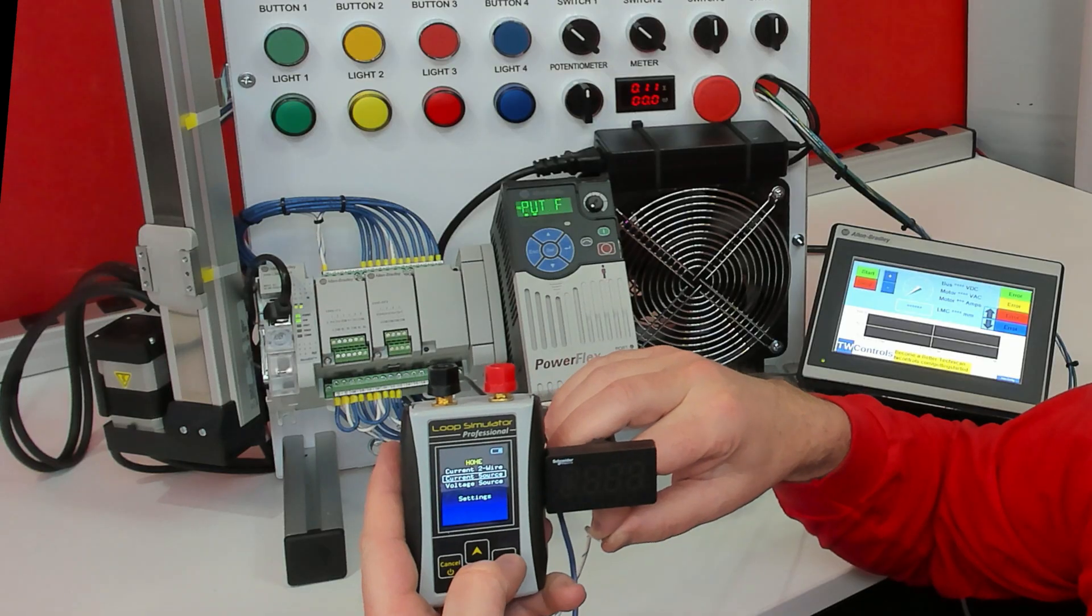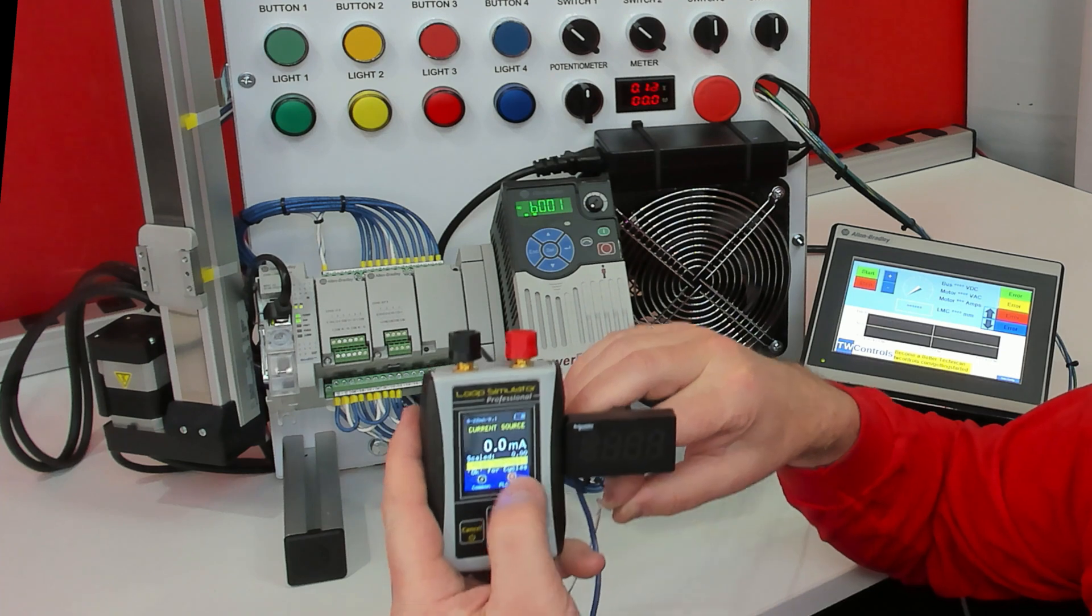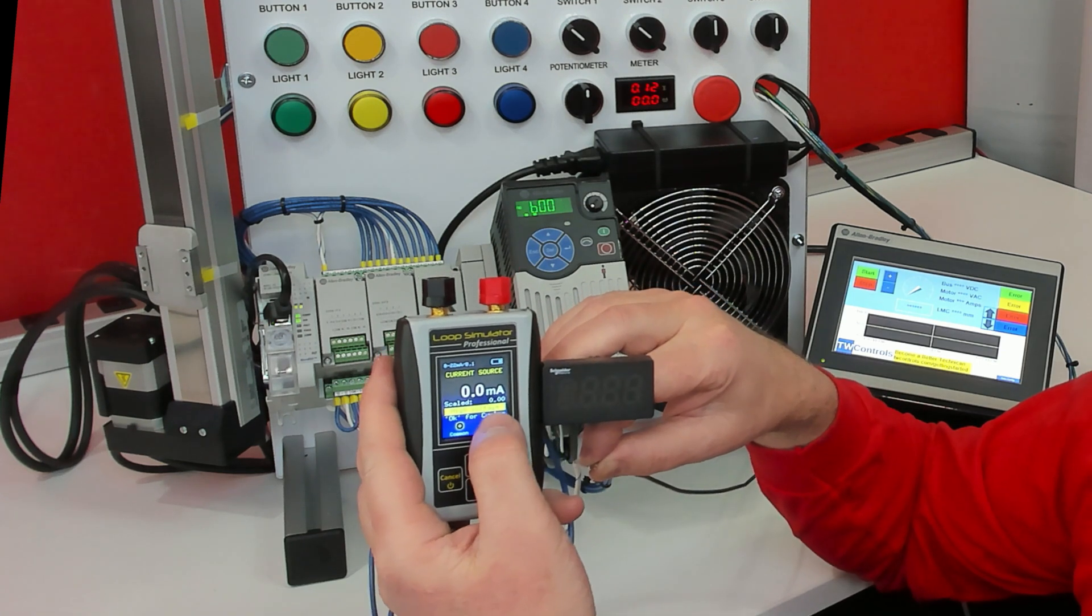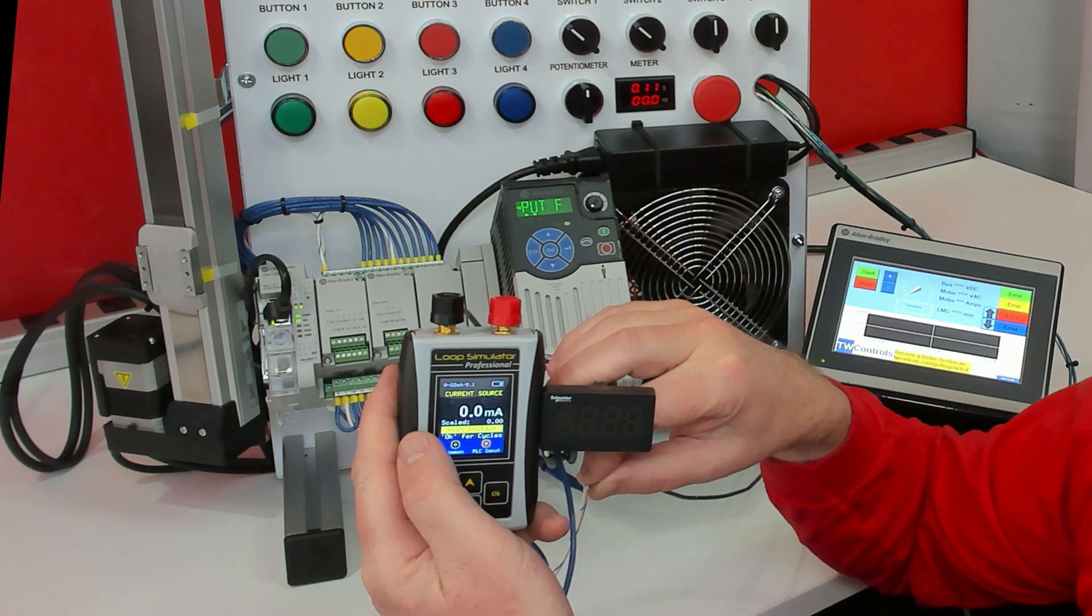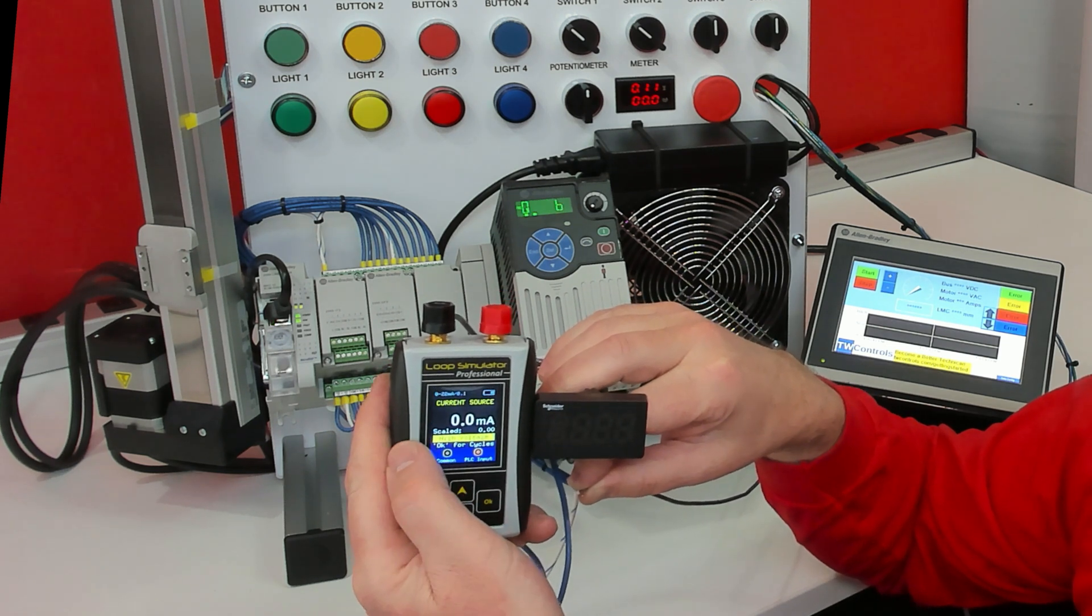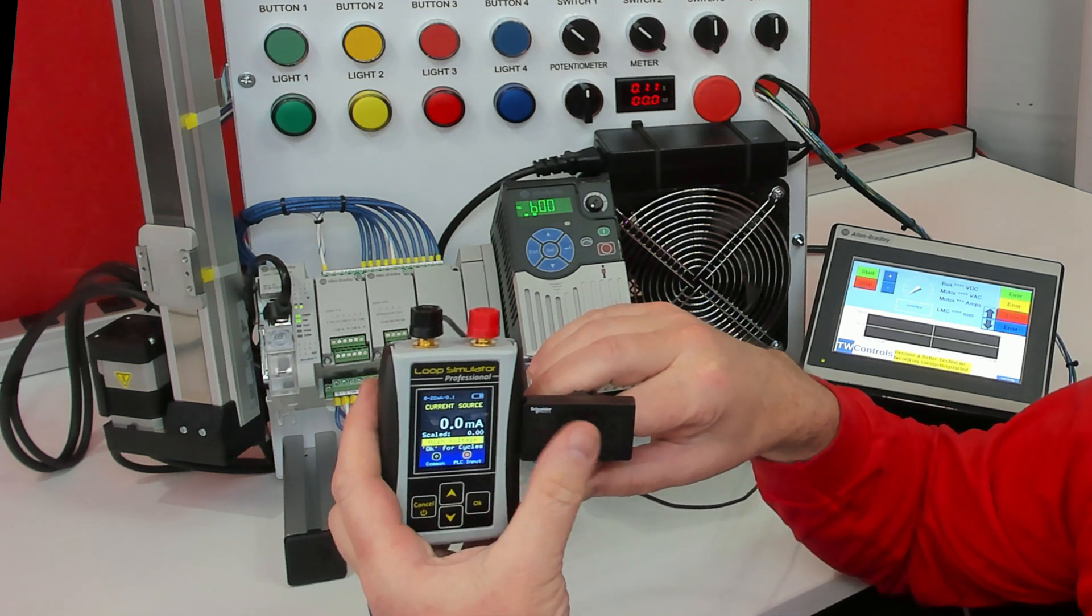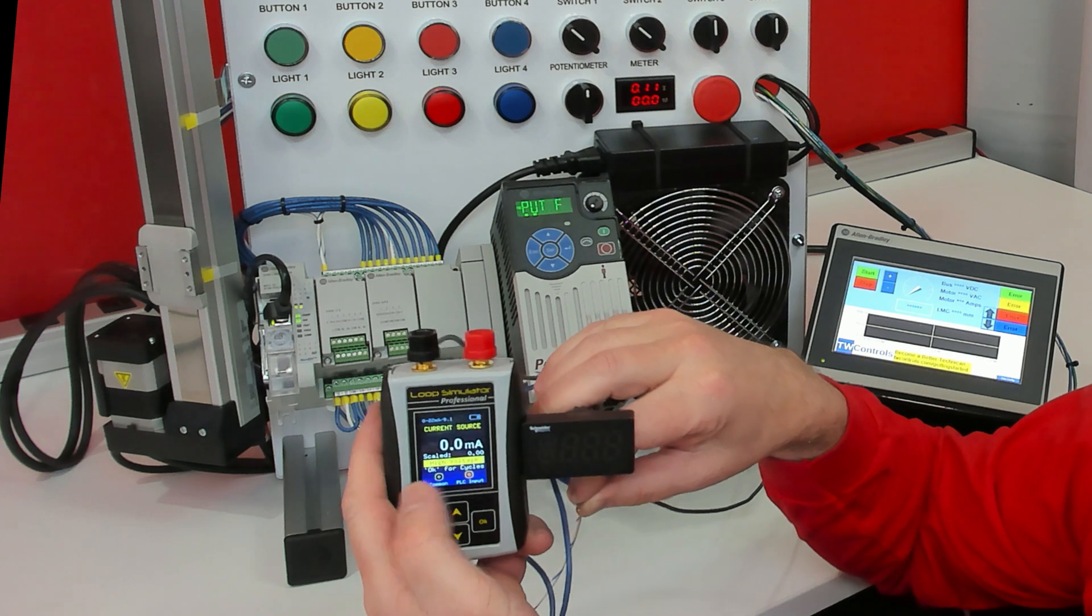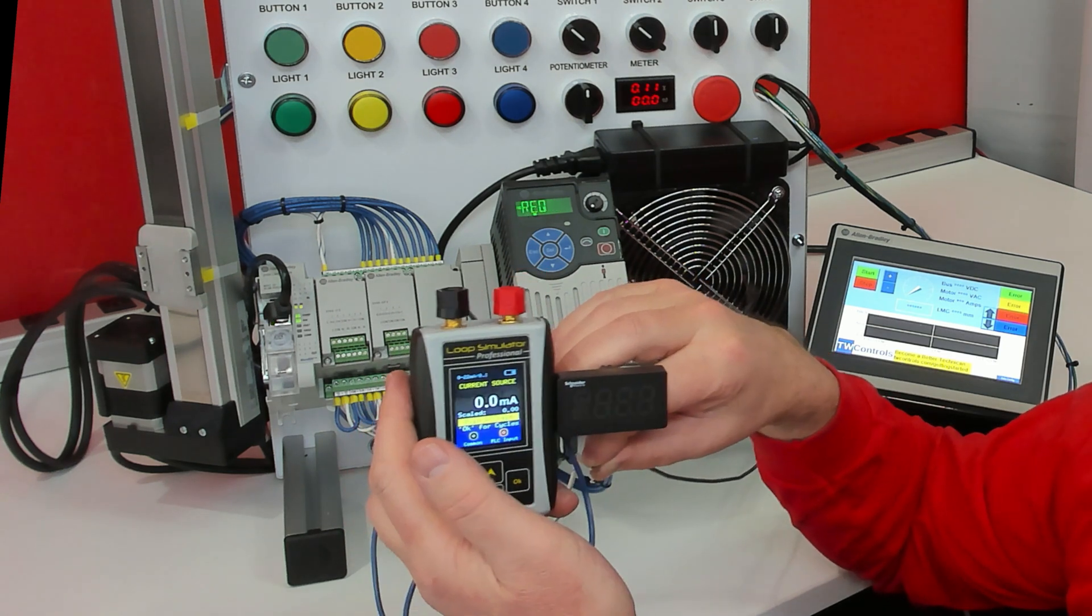Now we'll select current source. And notice right away, it says high voltage right here. And so that means the analog simulator is saying I have way too much voltage because I have my internal power supply voltage and I have this PLC trainer's power supply voltage. And I'm not going to let you do it. Whether you have no power supply in the loop or you have two on the loop, you're going to run into problems.